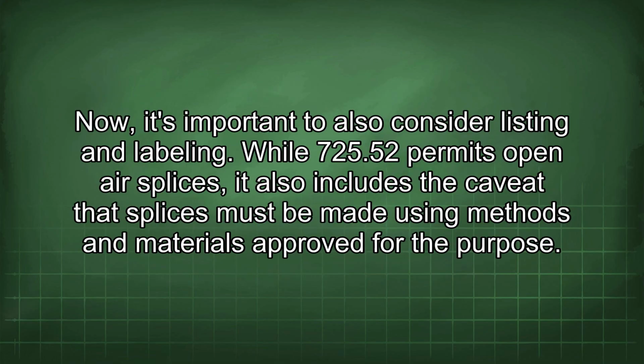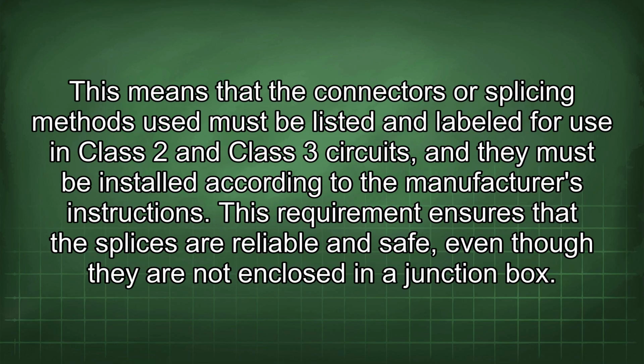Now, it's important to also consider listing and labeling. While 725.52 permits open-air splices, it also includes the caveat that splices must be made using methods and materials approved for the purpose. This means that the connectors or splicing methods used must be listed and labeled for use in Class 2 and Class 3 circuits, and they must be installed according to the manufacturer's instructions. This requirement ensures that the splices are reliable and safe, even though they are not enclosed in a junction box.